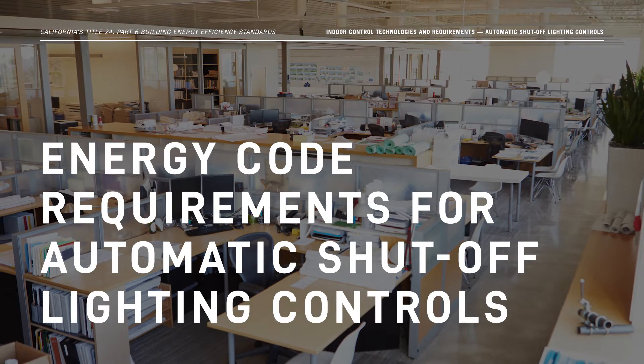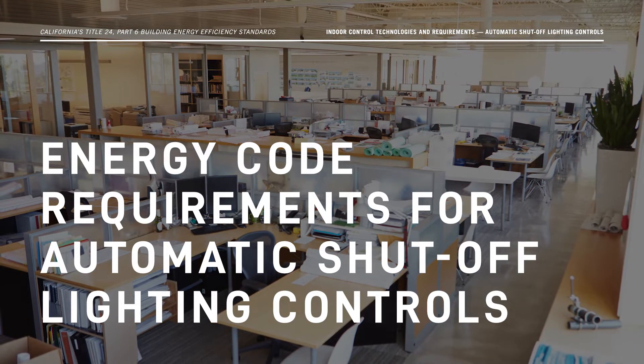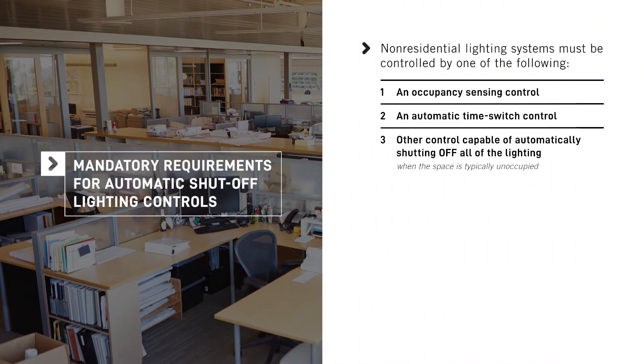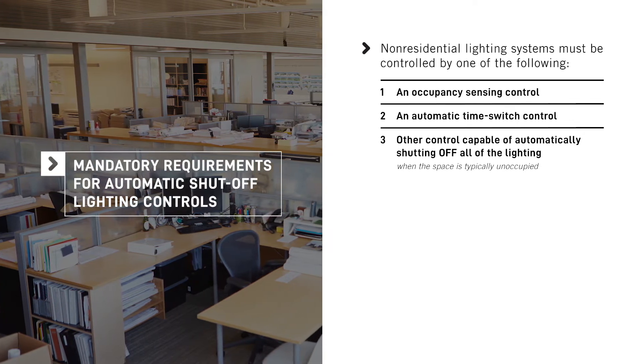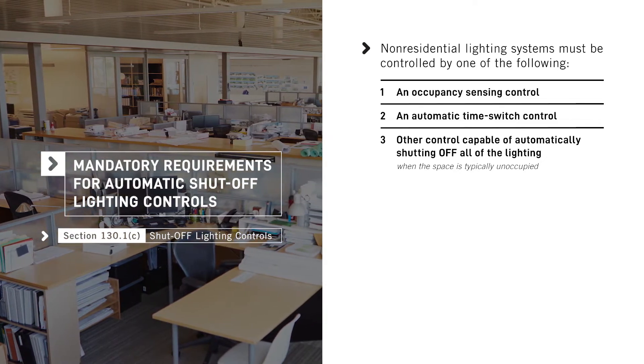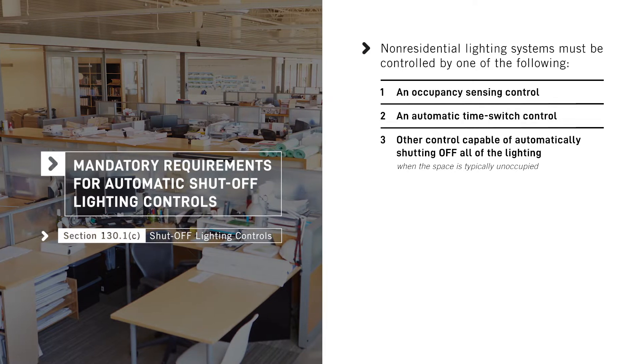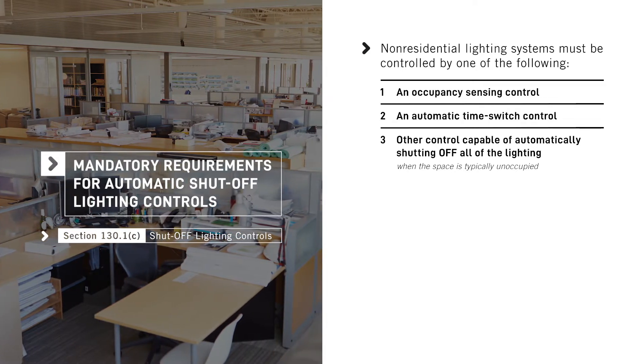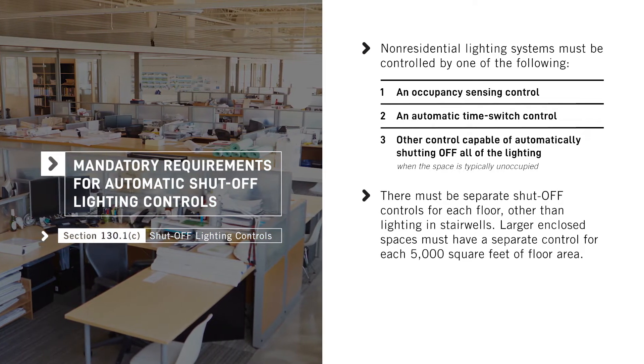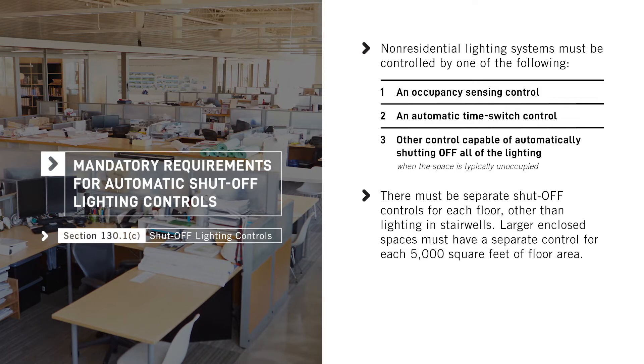Now let's discuss the specific mandatory requirements for indoor automatic shutoff lighting controls. The general requirements in Section 130.1c state that non-residential lighting systems must be controlled by either an occupancy sensing control, automatic time switch control, or other control capable of automatically shutting off all lighting when the space is typically unoccupied. There must be separate shutoff controls for each floor, and for larger enclosed spaces a separate control is required for each 5,000 square feet of floor area.